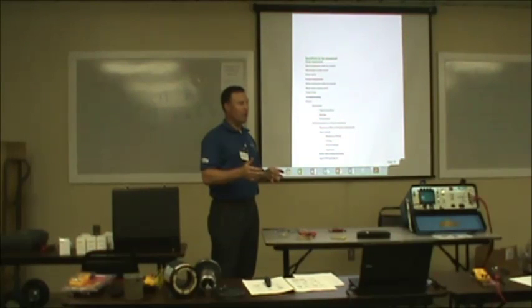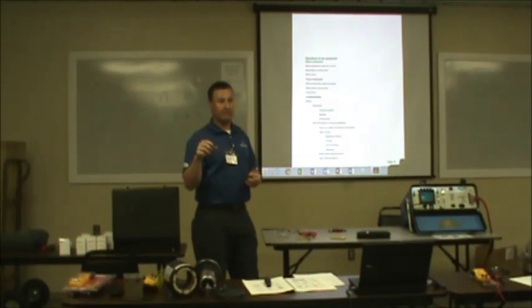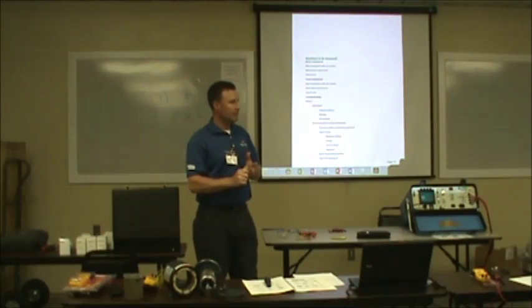I mean, it was unreal. But we did determine that the RTD on the motor was bad, giving a false reading. So we replaced the RTD, and I think the problem went away.